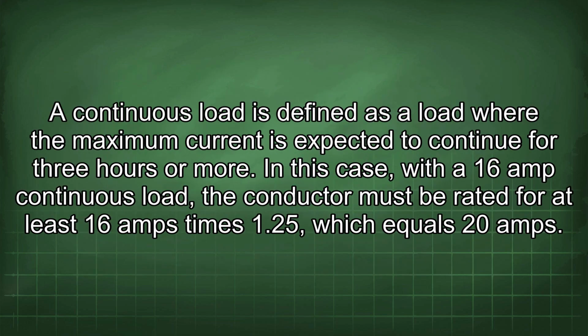A continuous load is defined as a load where the maximum current is expected to continue for 3 hours or more. In this case, with a 16 amp continuous load, the conductor must be rated for at least 16 amps times 1.25, which equals 20 amps.